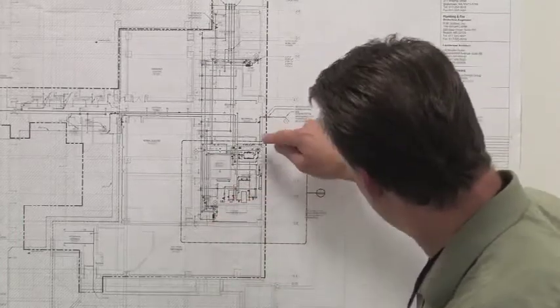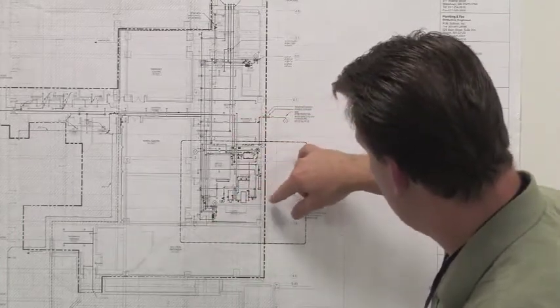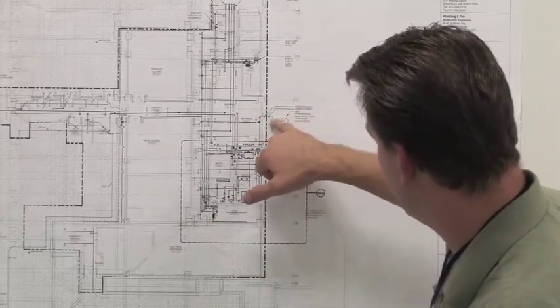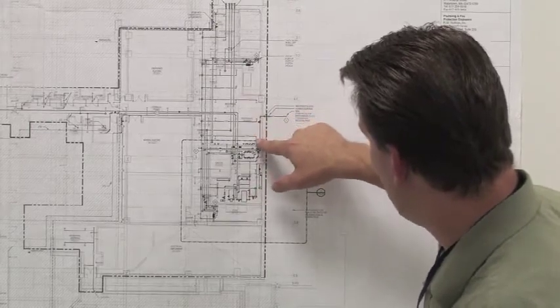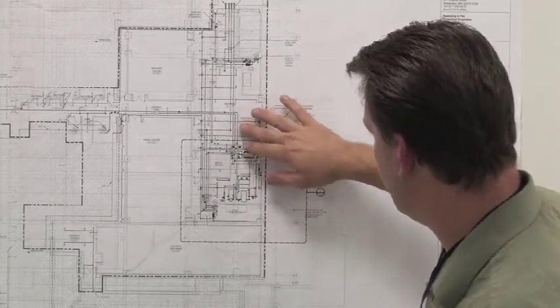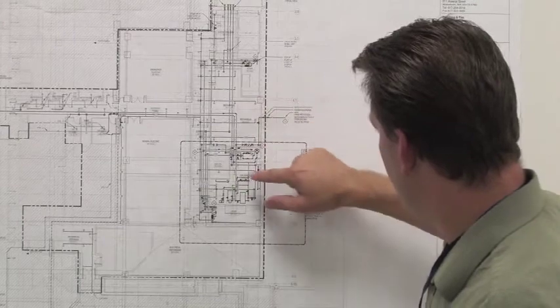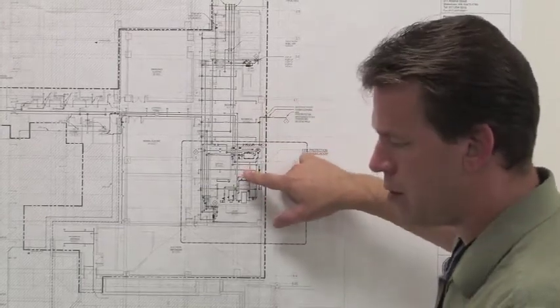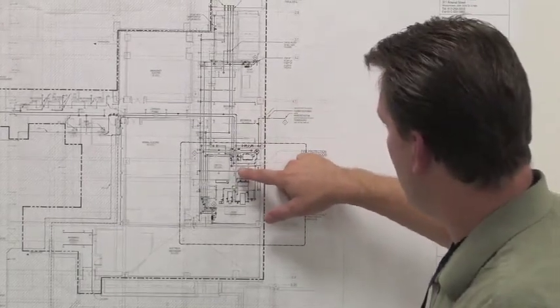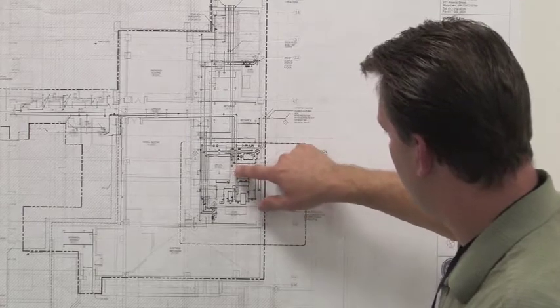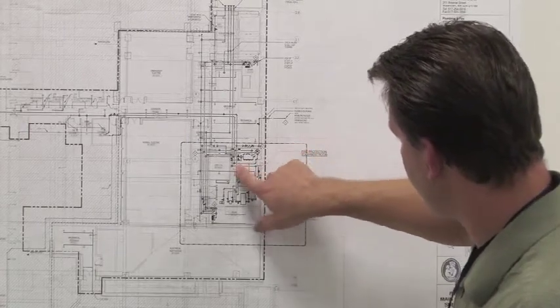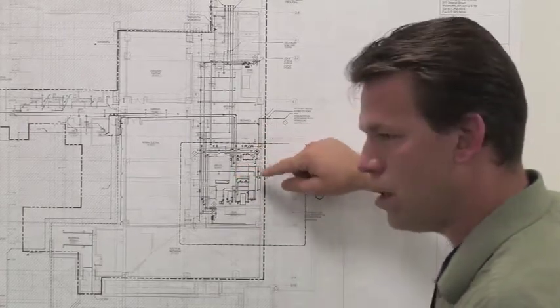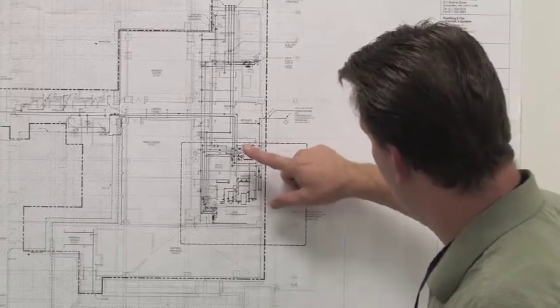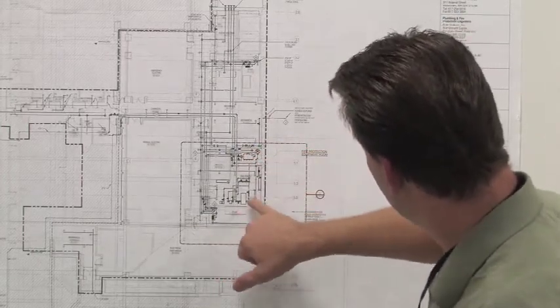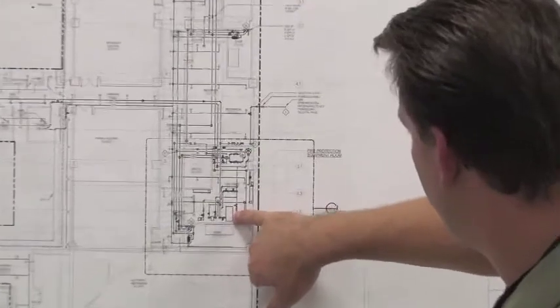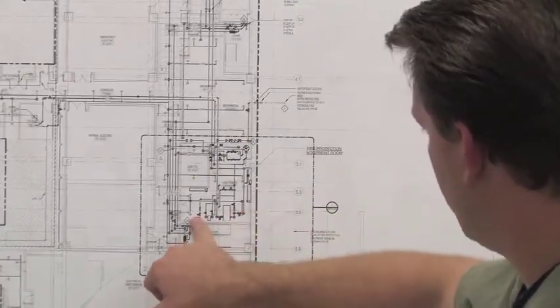And there's a new service coming in there, correct. Fire protection service coming in here, off of Binney. Double check valve inside the mechanical room adjacent. The access to the water storage tank is inside the fire pump room in this corner over here. Is that a floor hatch? Right. This is the horizontal fire pump, and next to it is the vertical fire pump.